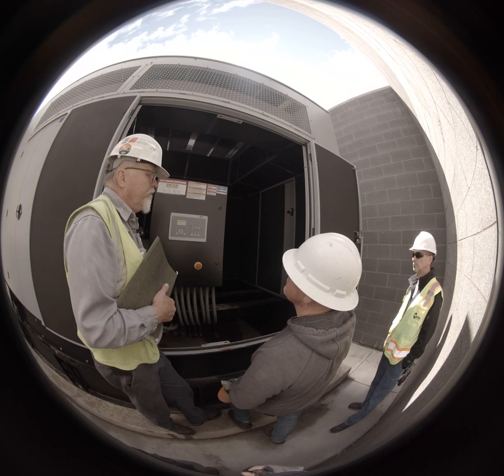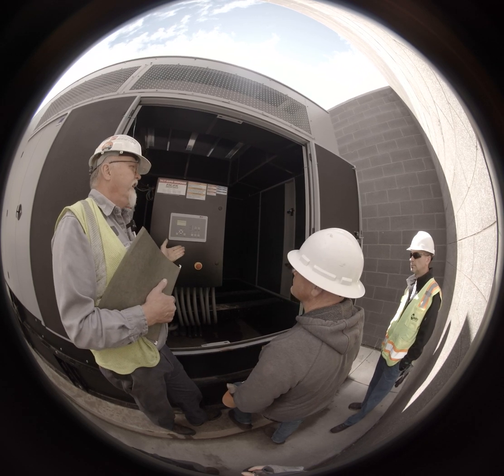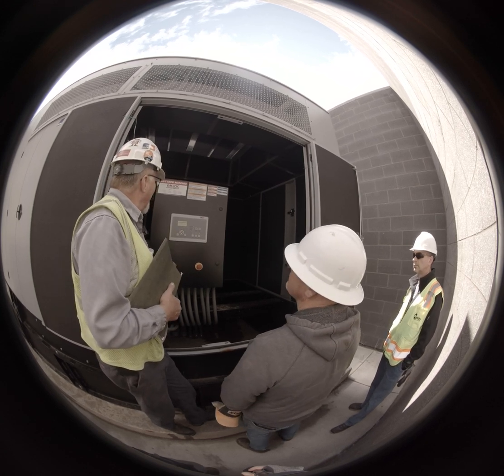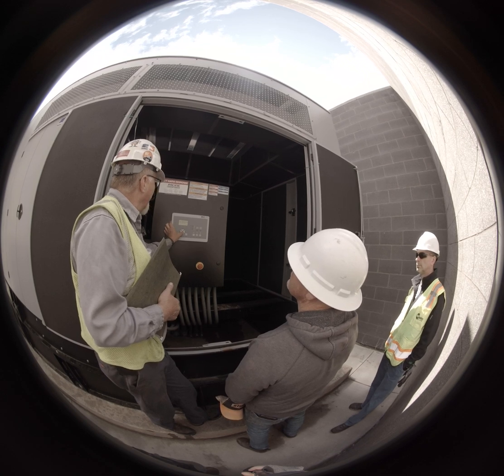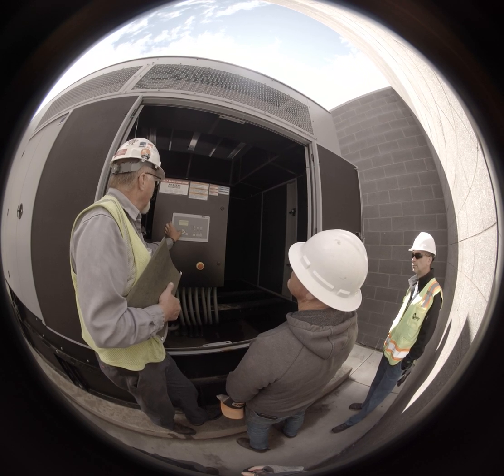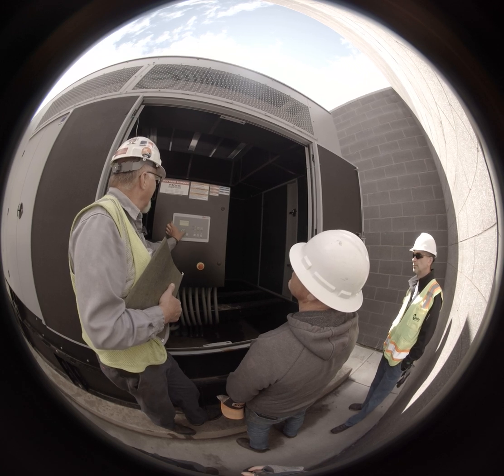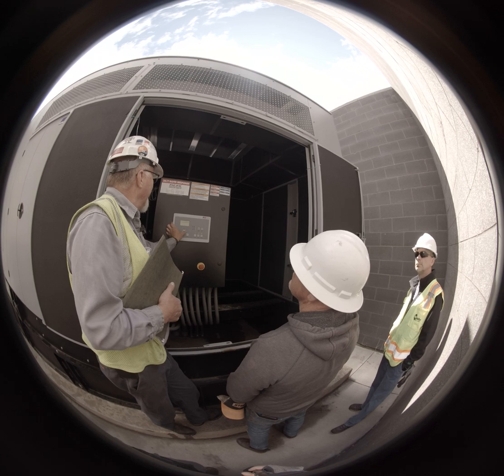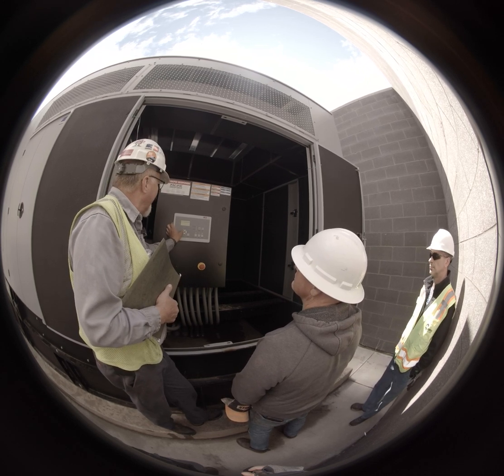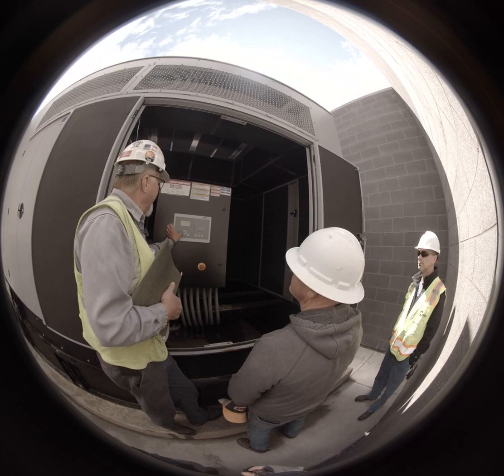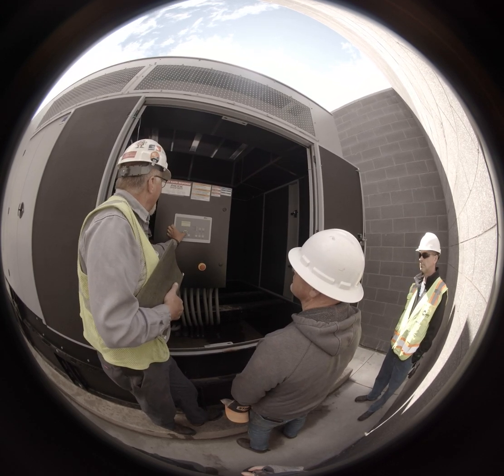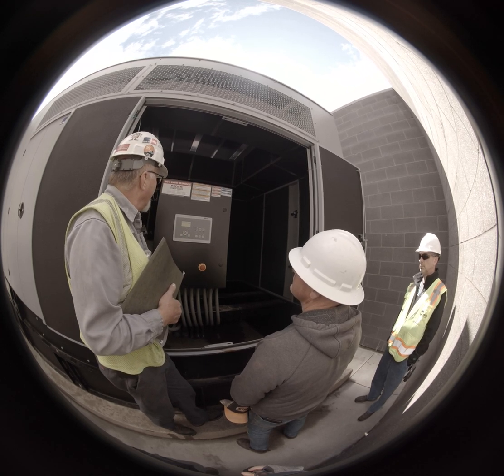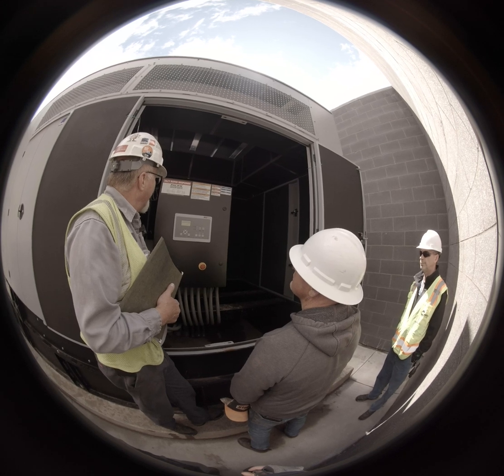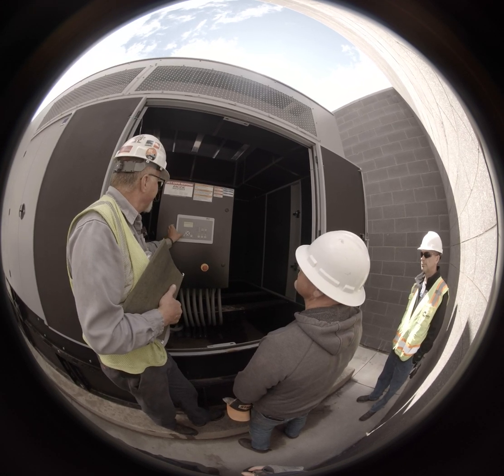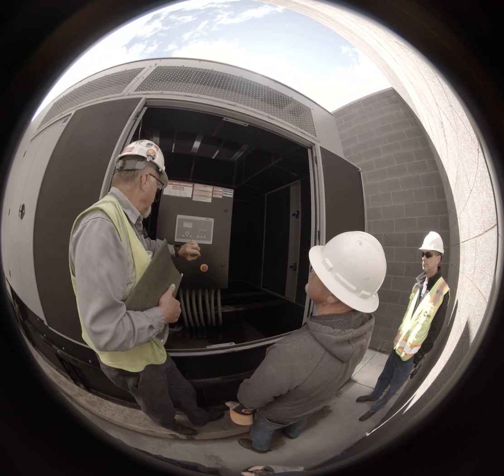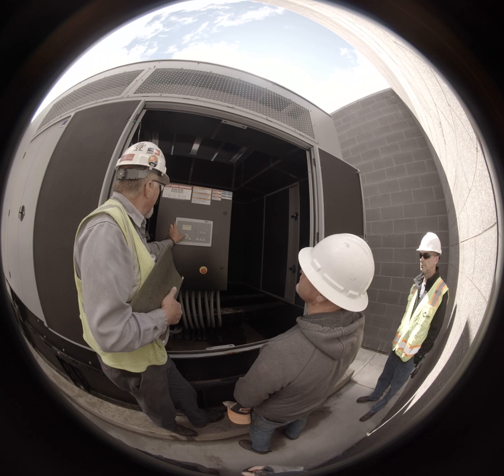Okay, session. Session is the most recent time. So if you come in here and say, yeah, the generator fired up last night, why? Okay. It didn't even elapse any time the last time they did this. Either that or they disconnected the batteries. They might have had the batteries disconnected on it, because normally it'll say your last run on it. Either that or somebody just bumped the starter. And under session, what time it started, and how many kilowatt hours. So it's 6:14. Yeah. So.